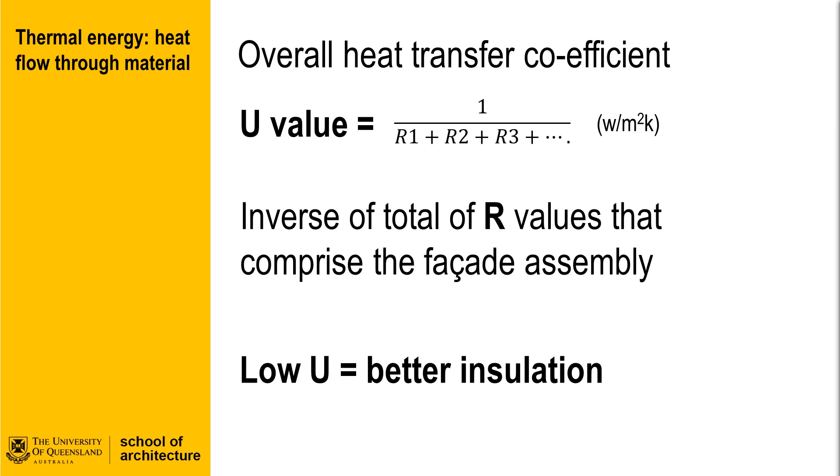Calculating the effect of these combined R values, we can then compare one wall assembly to another, and this is known as the overall heat transfer coefficient, or U value. The U value is an inverse of the sum of all R values that comprise a wall assembly. The effect is that a lower U value for a wall, the better the insulation value and resistance to heat flow for the wall.